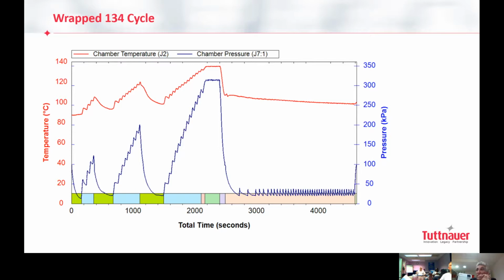When we are talking about a Class B model, there are two conditions. Class B is defined in the EN 13060, which is the European standard. Soon it will take place in the American standard because they are following the same concept. So what is this Class B process, and what's the difference between this process and the Class N/S process? There are two conditions in order to comply with Class B. And Class B is a process, not a machine, because you may have a machine which is Class B and still running Class N or S cycles in this so-called Class B machine.